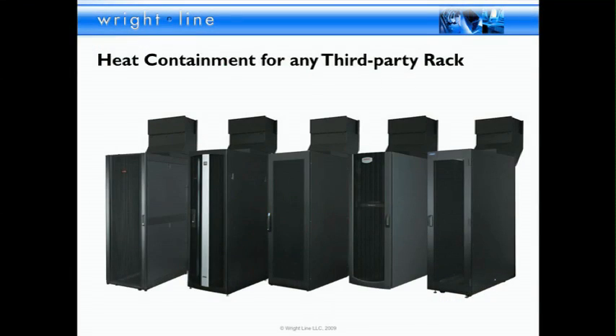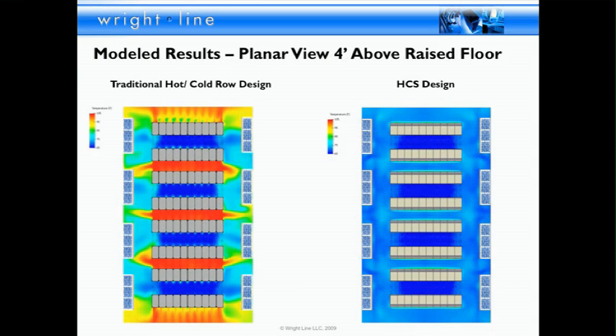Obviously, this is scalable. It's flexible. You can install it on an existing data center. We've done that multiple times with multiple vendor products, even on our own products, putting on this chimney-based system, connecting it up to a return plenum, and drawing the air directly back. It fits on all third-party racks, and it fits on our rack as well. We have a bunch of different CFDs, but I just wanted to capture one and throw it up here to be able to speak to it.